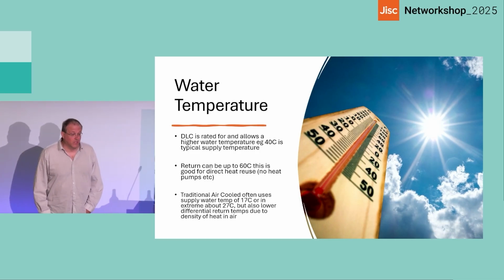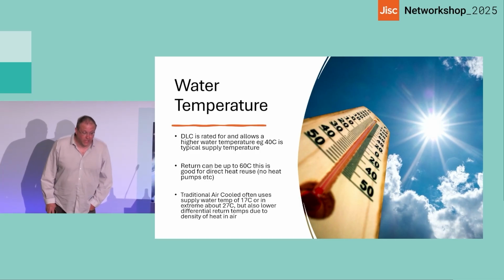So water temperatures. You'll find with DLC, you can get a lot higher water temperatures. Most of the DLC equipment will happily run at 40 degree input temperature for water. Some of them will even run higher, so you can get away with a lot. Return temperatures, 60C is about average these days. If you're pushing them hard, that 60C water, as you can see from the previous talk, is actually a pretty much usable temperature for a lot of things. So good returns on that.